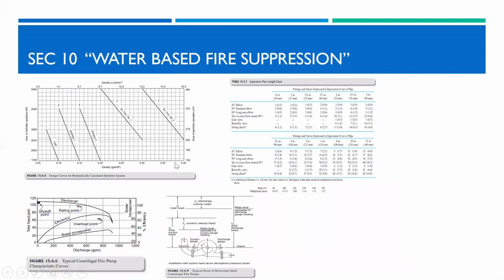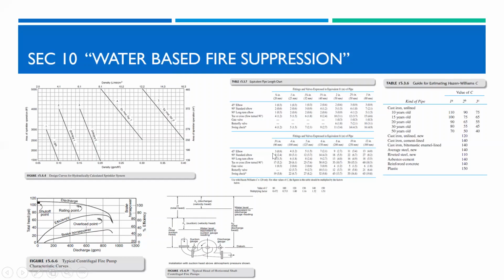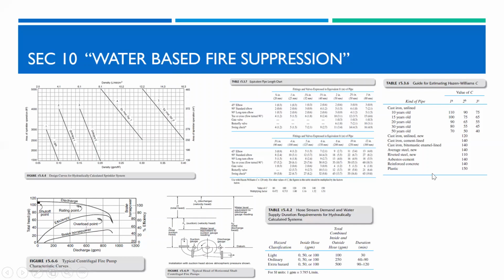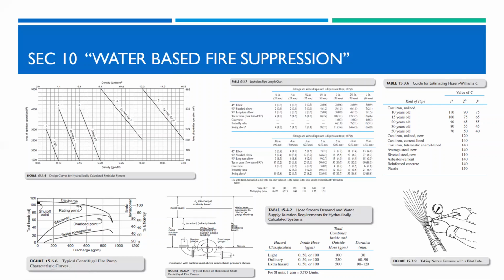Water-based suppression, like the density area curve based on the hazard. You can specify density and the area of operation in order to calculate the flow rate of the pump. To select the pump, we have to use the HQ curve here with the shut-off point or churn pressure point. We have the overload point and the rating point, efficiency, discharge, and brake horsepower of the motor. Here we have types of heads at suction and discharge of the pump and total head, and an equivalent length table for fittings and valves. Here we have the C values of hazard applications based on type of pipe, size, and age. We also have hose stream demands based on type of hazards and durations. And we have here how to measure the pressure of a hose or hydrant using a pitot tube.